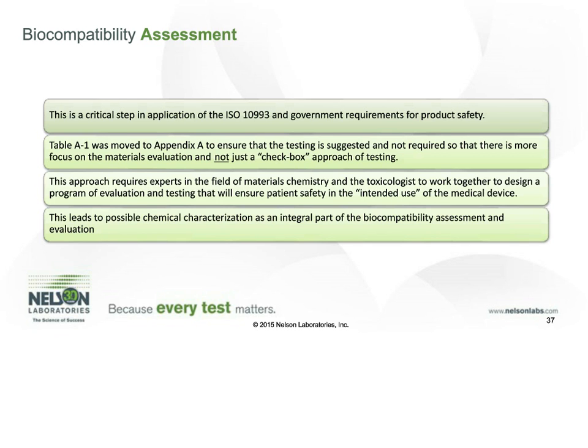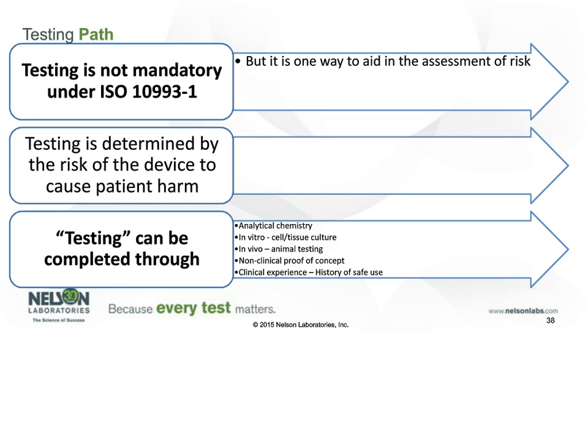And the last one right there on that slide is chemical characterization is an integral part of biocompatibility assessments and evaluation. I do want to put a little caveat there for certain devices. I talked about low-risk devices that have minimal contact with the body or certain materials. These may not need a chemical evaluation or a full-blown leachable extractable profile to come up with a successful evaluation. But for certain devices that have a more aggressive type of contact, the chemical characterization is an essential part of a biocompatibility assessment. So to sum up this beginning part, testing is not mandatory under 10993-1. It's just one way to address risk associated with your device, but there are other ways to do so. That testing is determined by the risk of the device to cause the patient harm, and we want to address those risks through it.